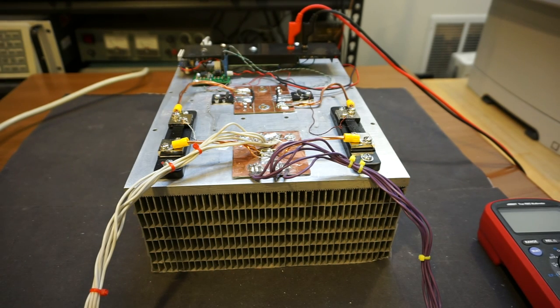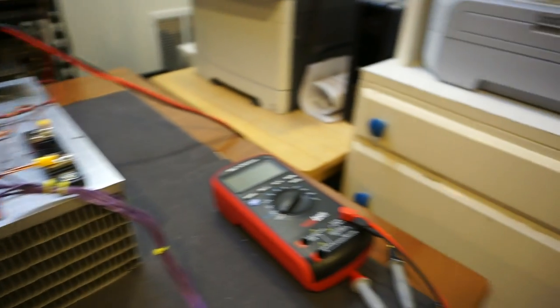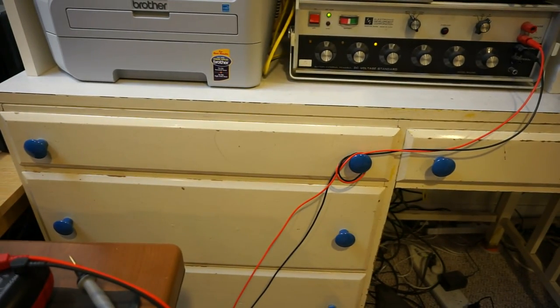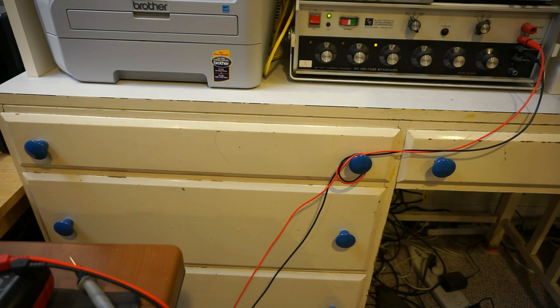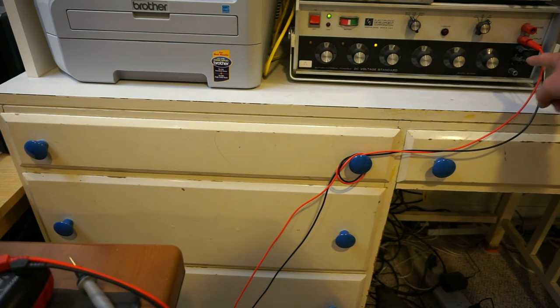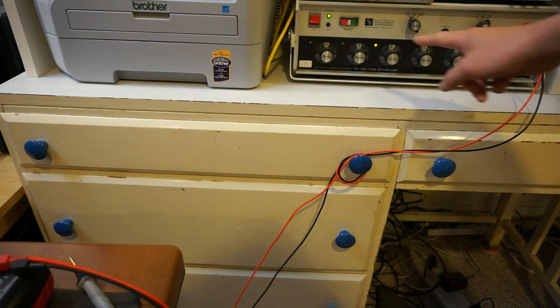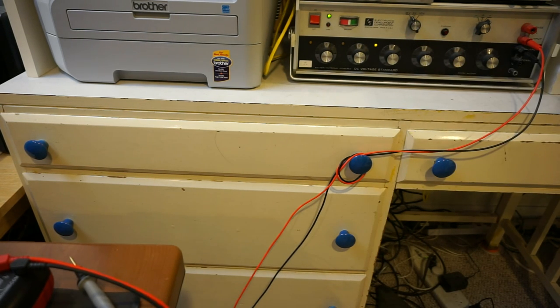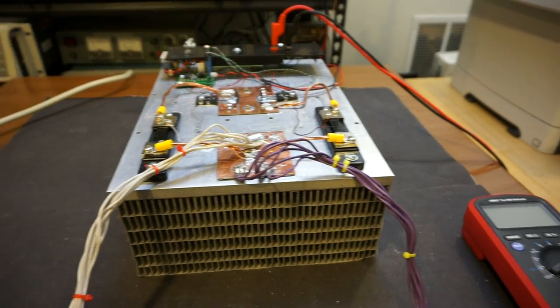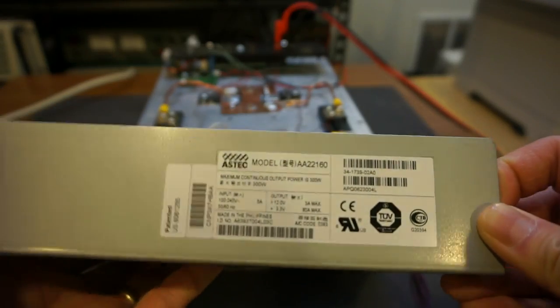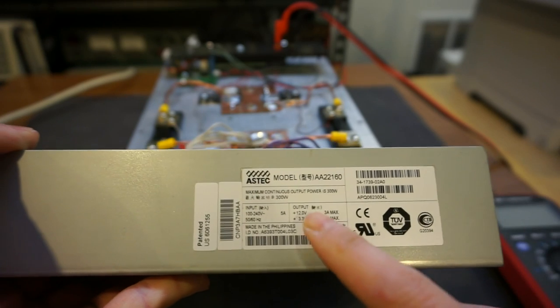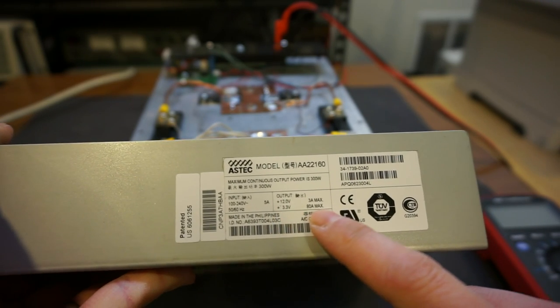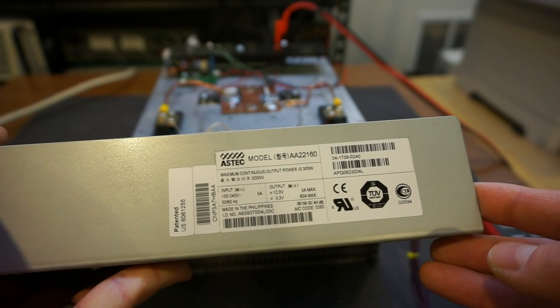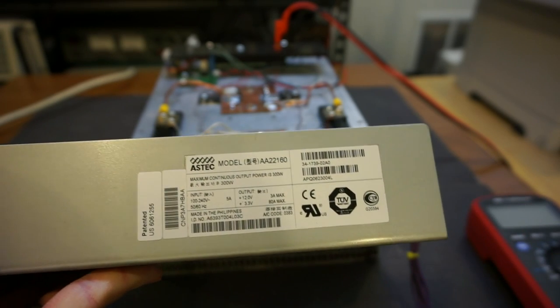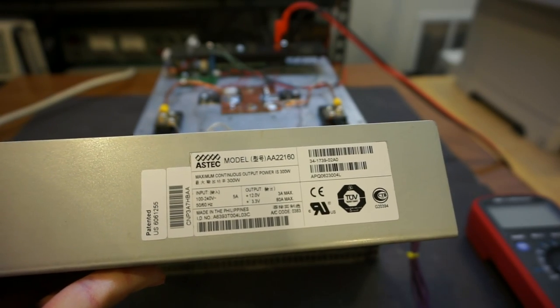And here's our experiment setup. The control voltage is input from this voltage standard. Right now I set it to millivolts mode so that I can finely control it down to 1 microvolt. Of course, we're only going to be interested in the millivolt range today. The first power supply I'm going to test is this ASTEC model that you saw before. One interesting thing about it is it has a 3.3 volt power rail that is capable of outputting 80 amps max. That's the rail we're interested in.